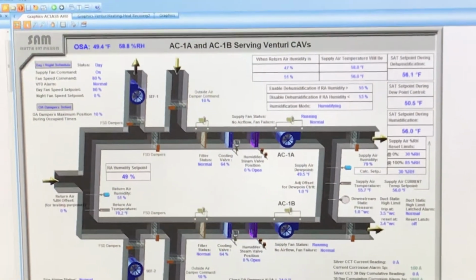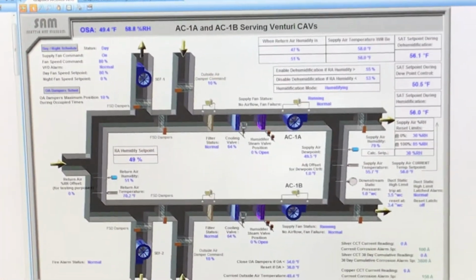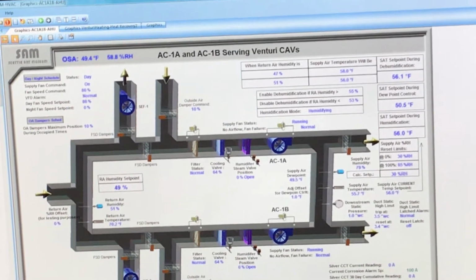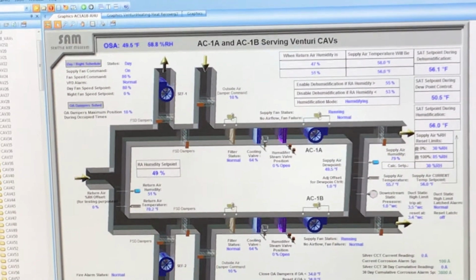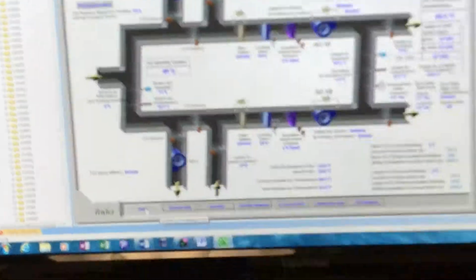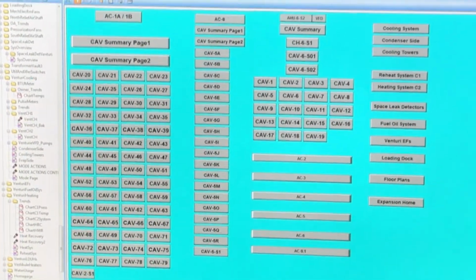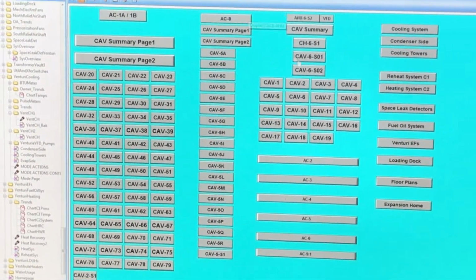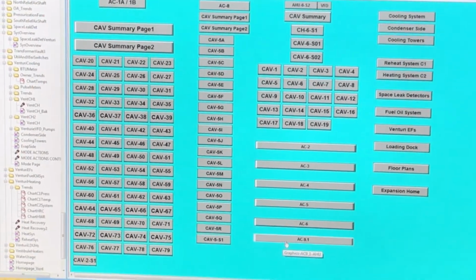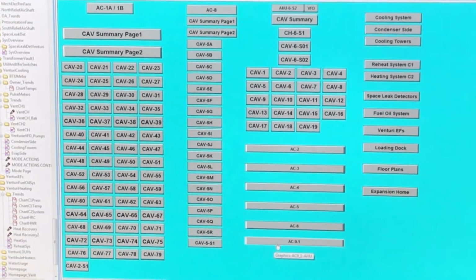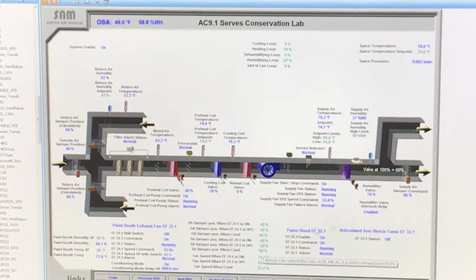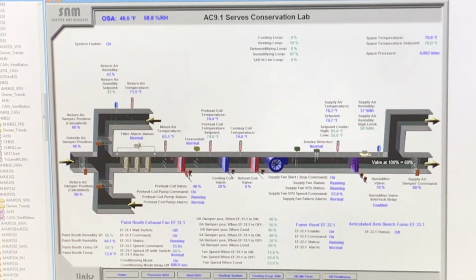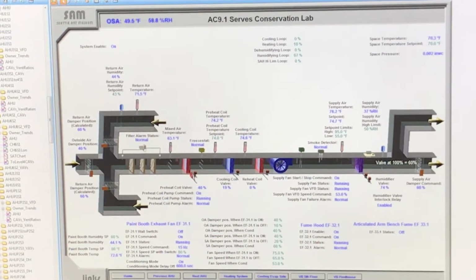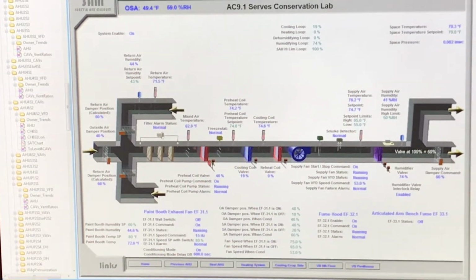which I don't know if that's going to be an issue down the line, going back, because that's the main air handler for this building. Yes, I think I talked to Sam, the engineer. Yeah, I mean, he checked the calculation. He said that even with both valves closed, there is sufficient three-way and water flow to guarantee the minimum flow through the chiller. Okay. Because I thought we measured a kind of low value.